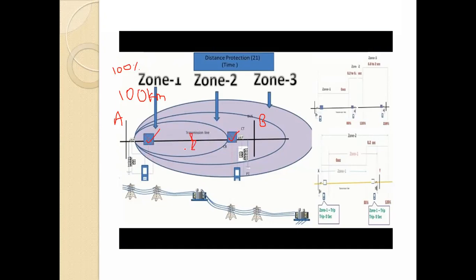At a time only 2 relays will operate. But what happens if the fault is occurring near the receiving end? Then the second relay will operate first and then the first relay will operate. So this is your first zone, covering 80% of this transmission line, and instantaneously your relay is operating within a fraction of seconds. If any fault occurs, your relay will operate instantaneously in zone 1.